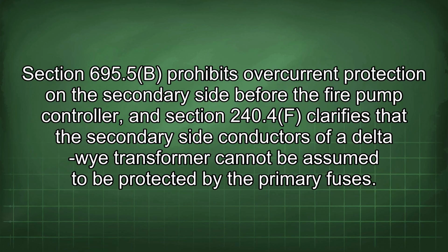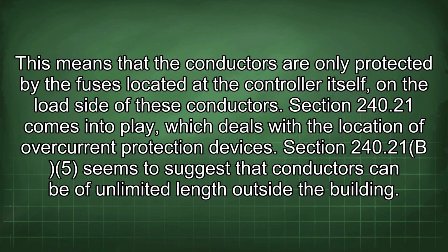Section 695.5(B) prohibits overcurrent protection on the secondary side before the fire pump controller, and Section 240.4(F) clarifies that the secondary side conductors of a delta-wye transformer cannot be assumed to be protected by the primary fuses. This means that the conductors are only protected by the fuses located at the controller itself, on the load side of these conductors.